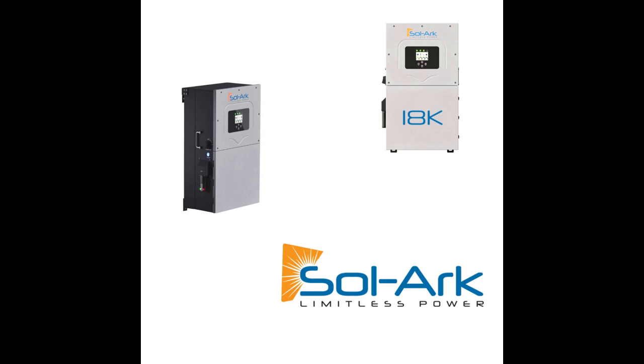Now, typically, what we're going to recommend is not to oversize the battery past 24 hours of the customer's load usage, because once you go past 24 hours, you start to get cost inefficient when adding battery. It makes more sense just to add a third-party generator to the mix with our system, since we have the capabilities to do it, the ease of integration, and you're going to have, again, a much more cost-efficient system for the customer and that tertiary source of power.